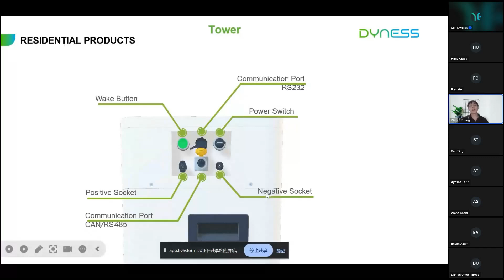The tower series is easier for parallel connection situations. You just need to connect the BDU to the combiner box, no need to do anything else for the battery modules down there. The parallel connection amount maximum is 12 clusters, which is 250 kilowatt-hour. You can use it in a residential site, like a house or a villa, or in a commercial industrial scenario.